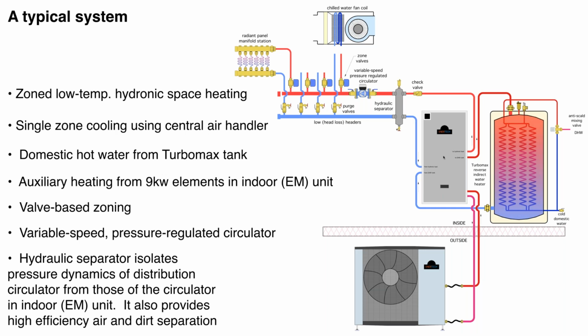So on space heating, what we're doing over here, we're showing a component called a hydraulic separator. Those of you that have been involved with hydronic systems for a while are probably familiar with this at this point. 10 years ago, this was a relatively unknown device in North American hydronics. Well, what it does is it basically separates the pressure dynamics that this circulator, we'll call that the distribution circulator, creates, versus the pressure dynamics of the circulator that's inside that indoor unit of the heat pump.